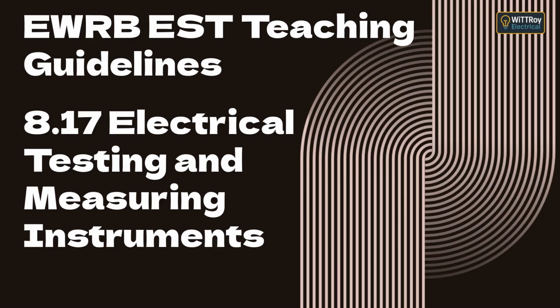5. Current test. Purpose: to measure load current under normal operation. Use a clamp meter to avoid breaking the circuit. Compare with the rated current on the nameplate. Excessive current indicates overload or faults. These are the standard verification tests specified in AS/NZS 3017 Clause 2.3.